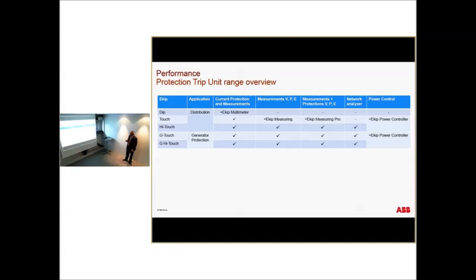The units, I gave you brief information before. Let's go into a bit more detail. So basically, we divide by application: distribution and generator protection. Let's stay on the distribution one. You need current protection and measurement. This is what we can do. You can do it with a Dip, with a Touch and High Touch. With the Dip, with the addition of multimeters. The measurement of voltage, power, and energy can be done only with Touch and High Touch. The protection, again, can be done with Touch and High Touch. The network analyzer is embedded inside the most sophisticated one. And then the control has to be done with the help of the Ekip Power Controller.